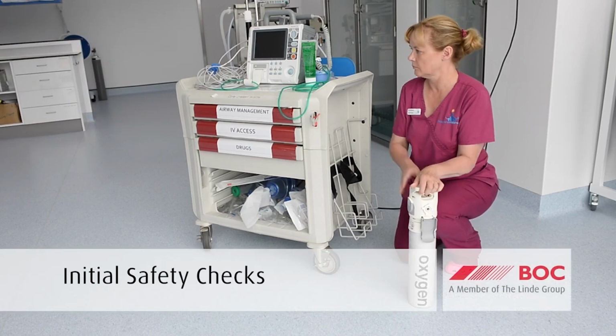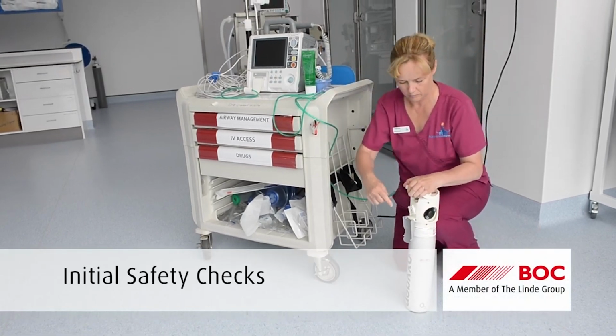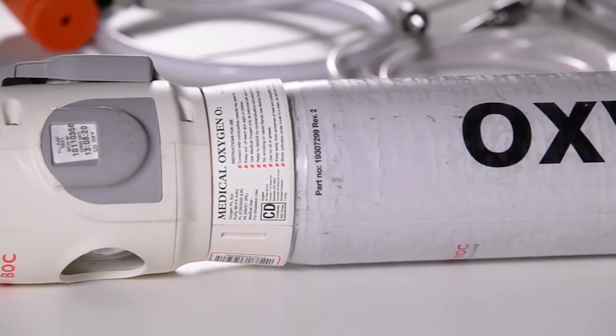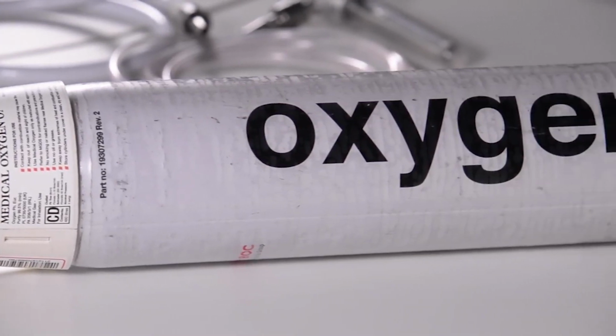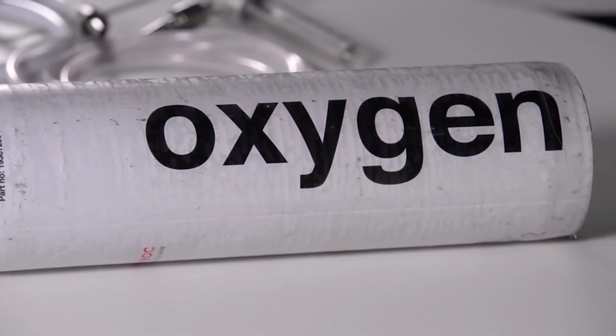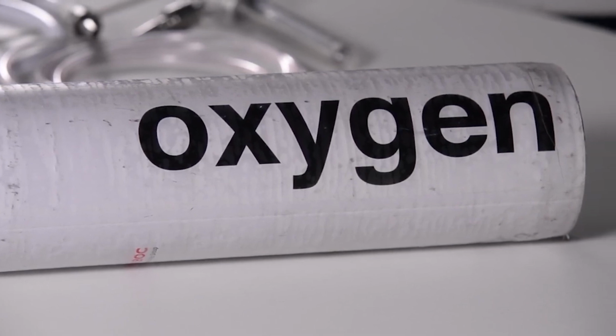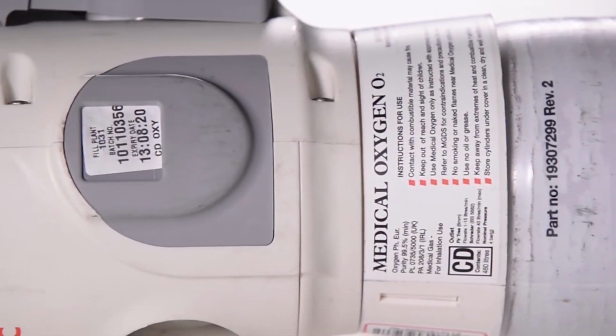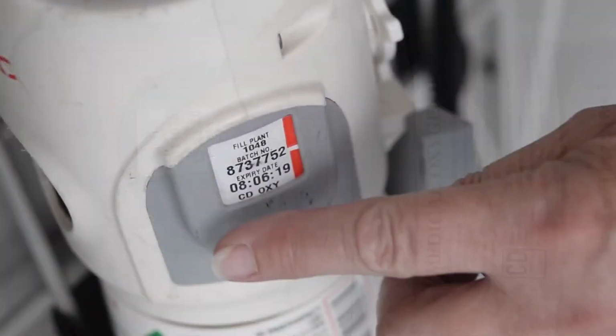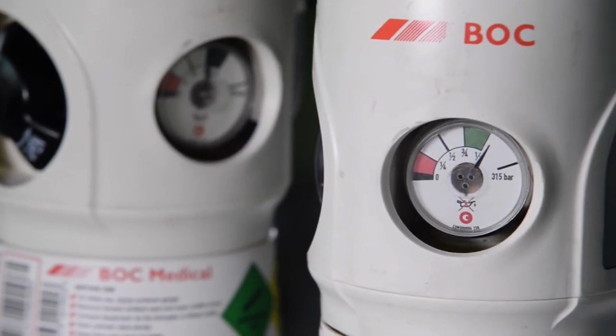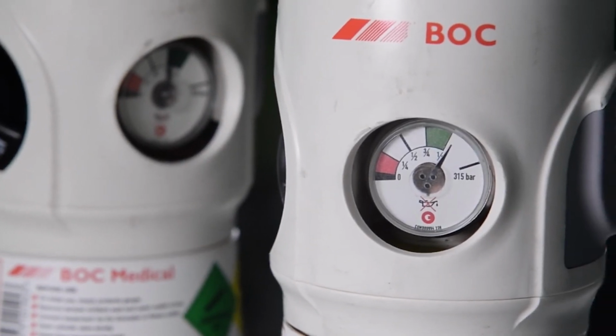Before handling cylinders, ensure your hands are clean. If you have been using alcohol-based gel or liquids to decontaminate your hands, make sure the alcohol has totally evaporated. When selecting the cylinder for use, check the cylinder is clean and free from any damage. Ensure the cylinder is free from oil and grease, particularly around the Schrader and fir tree outlets. Ensure you have the correct medical gas by checking the cylinder label. Check the expiry date on the batch label fitted to the cylinder. Make sure the contents gauge is in the green zone. This indicates that the cylinder is full.